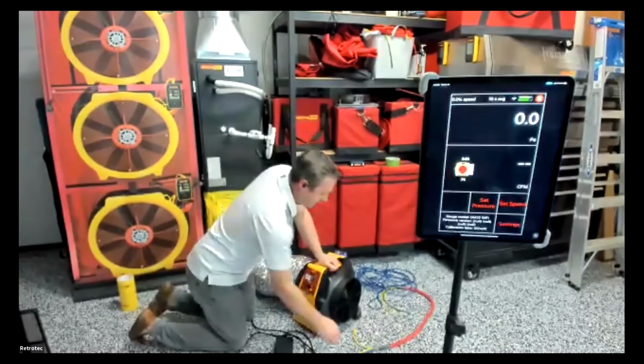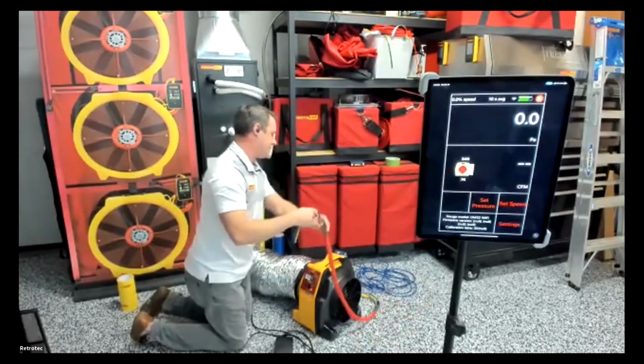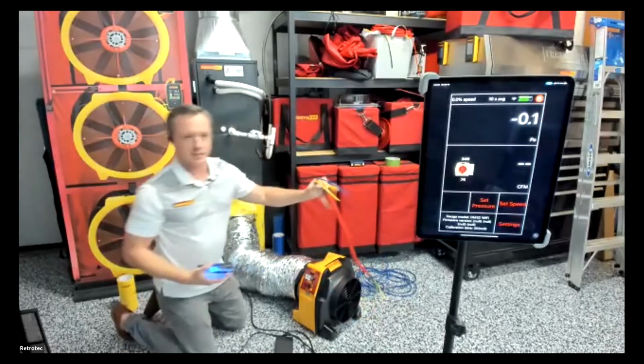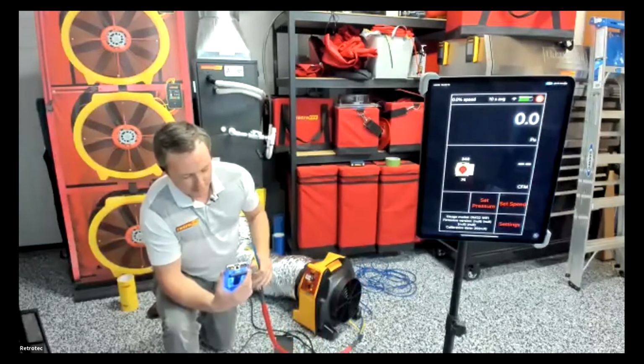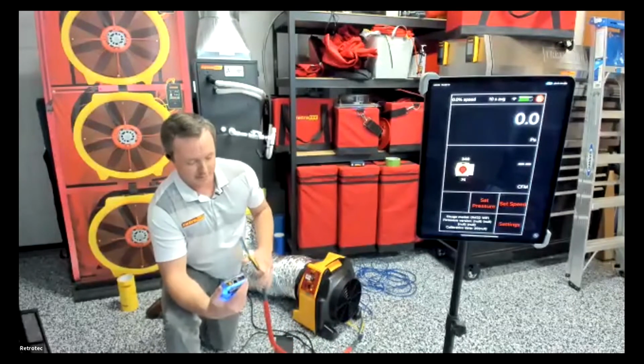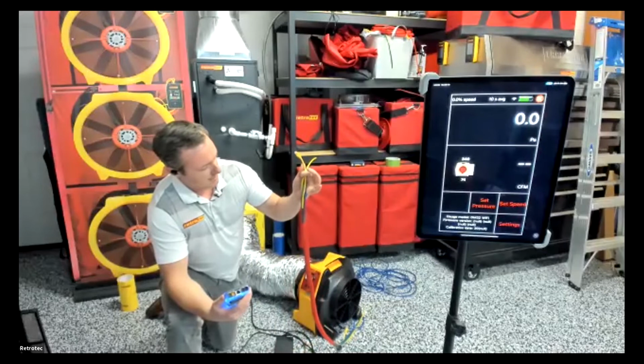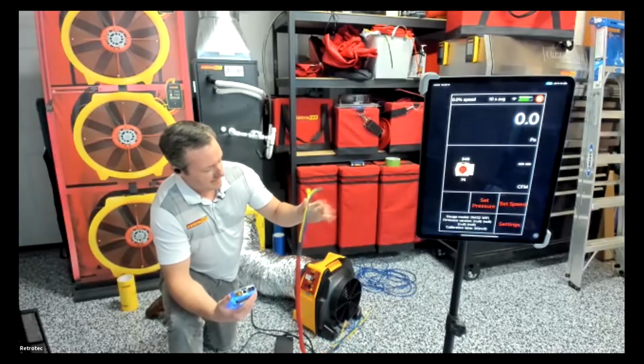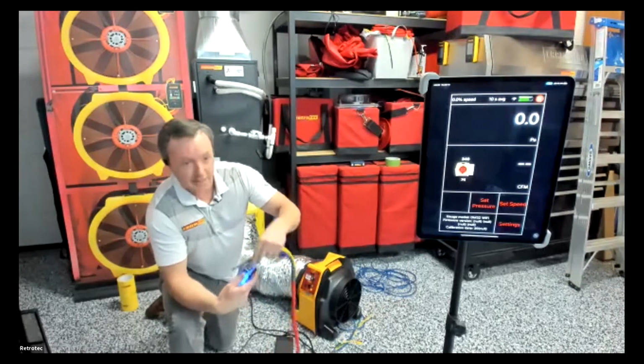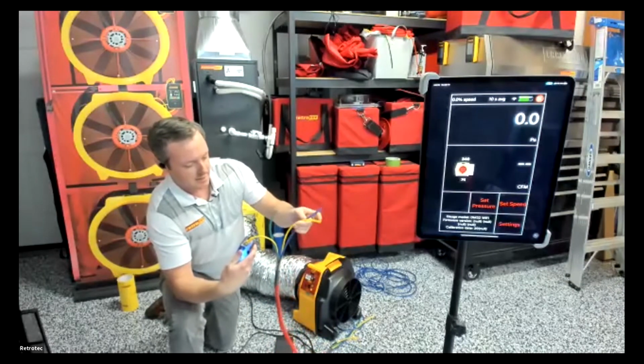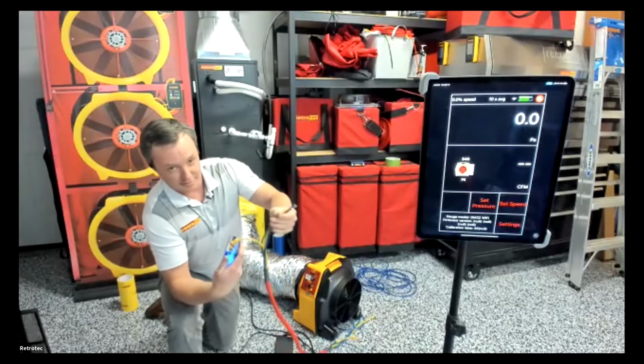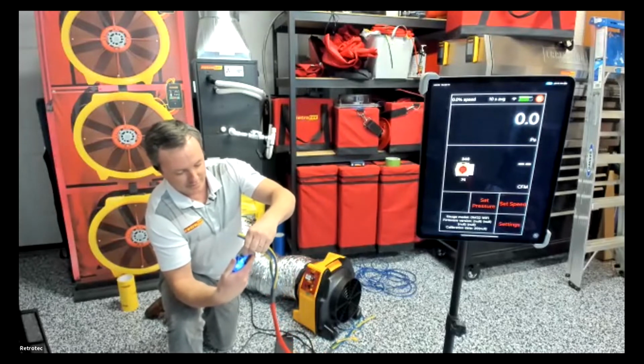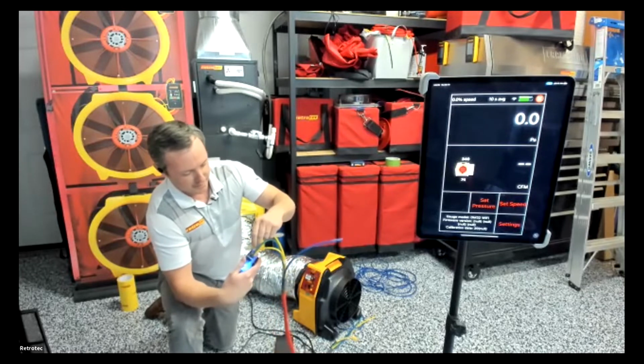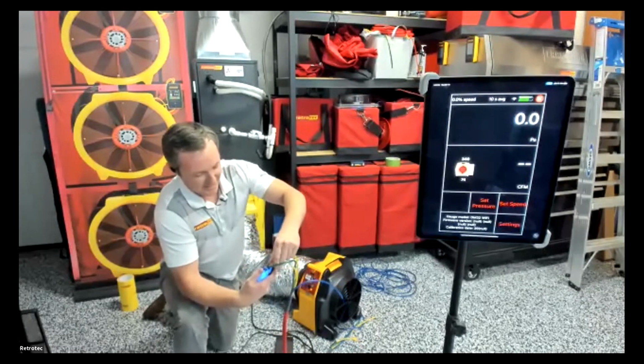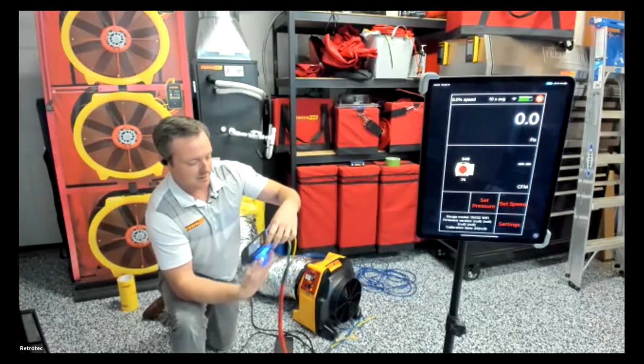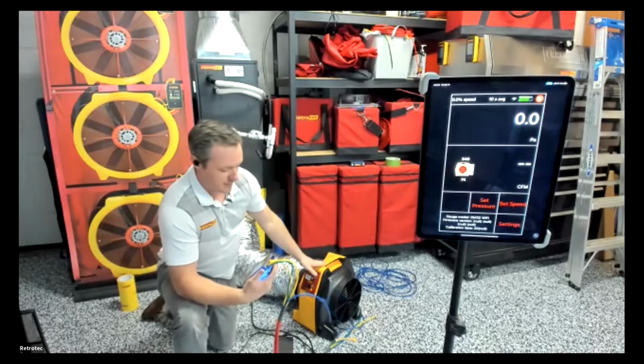I'll come up a little closer so you can see this next part. It's really easy - this is a feature unique to Retrotec, our color coding system. There's this umbilical that has the different tubing and the data cable. The data cable plugs into the top of the gauge. As you can guess, the green tube goes to the green port, and the yellow tube goes to the yellow port. This is on the channel B side of the manometer, so these two are reading fan pressure coming from the fan.